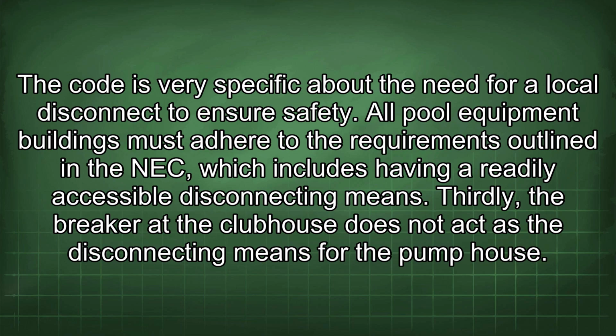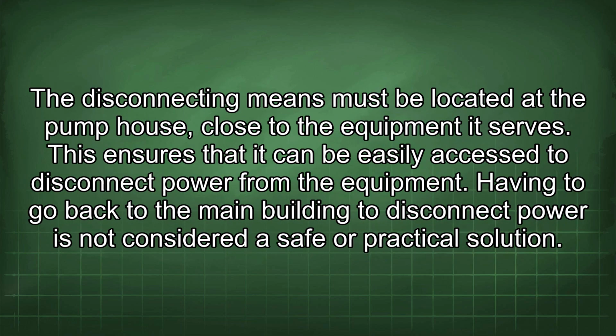Thirdly, the breaker at the clubhouse does not act as the disconnecting means for the pump house. The disconnecting means must be located at the pump house, close to the equipment it serves. This ensures that it can be easily accessed to disconnect power from the equipment. Having to go back to the main building to disconnect power is not considered a safe or practical solution.